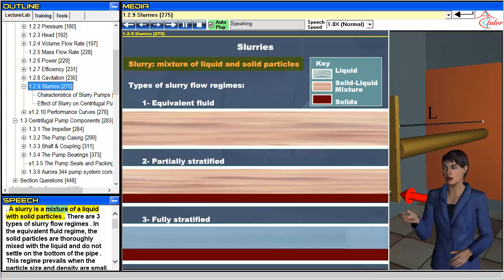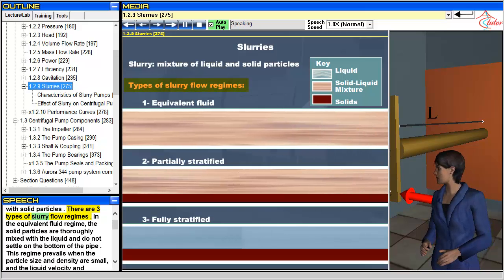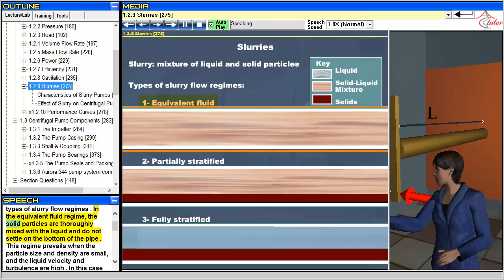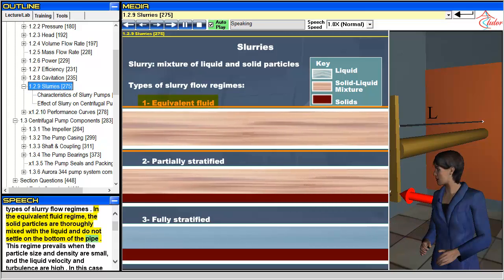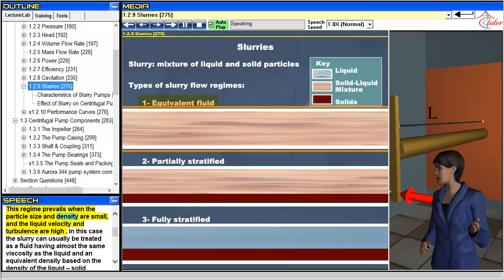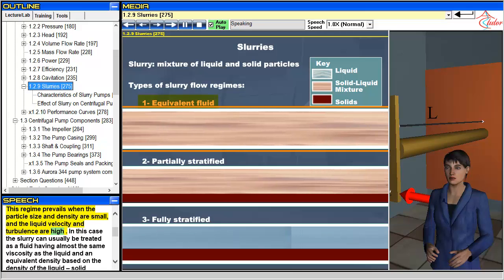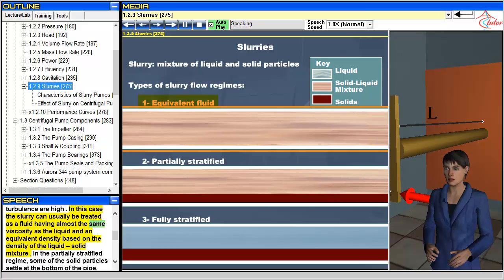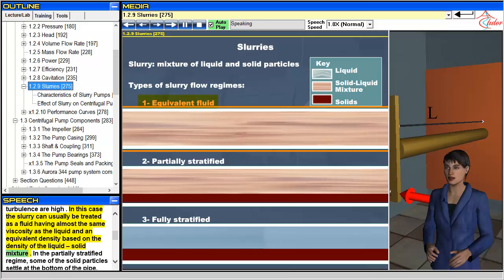A slurry is a mixture of a liquid with solid particles. There are three types of slurry flow regimes. In the equivalent fluid regime, the solid particles are thoroughly mixed with the liquid and do not settle on the bottom of the pipe. This regime prevails when the particle size and density are small, and the liquid velocity and turbulence are high. In this case the slurry can usually be treated as a fluid having almost the same viscosity as the liquid and an equivalent density based on the density of the liquid-solid mixture.